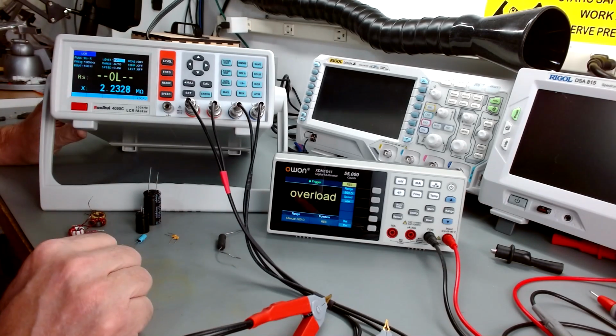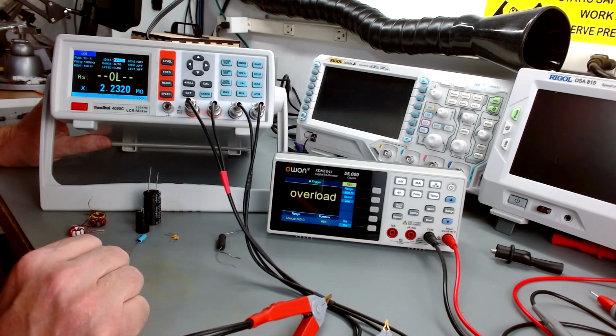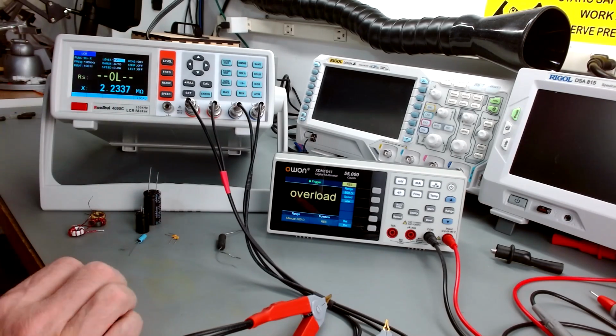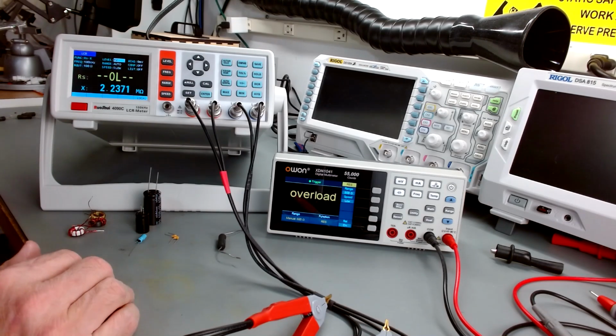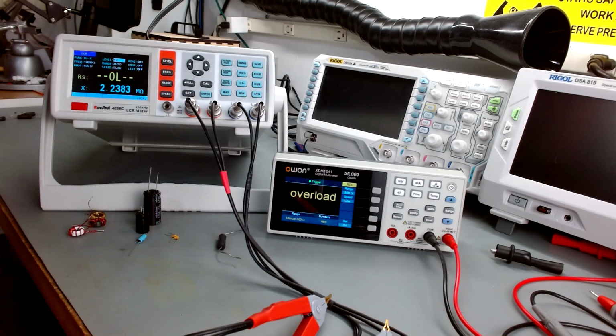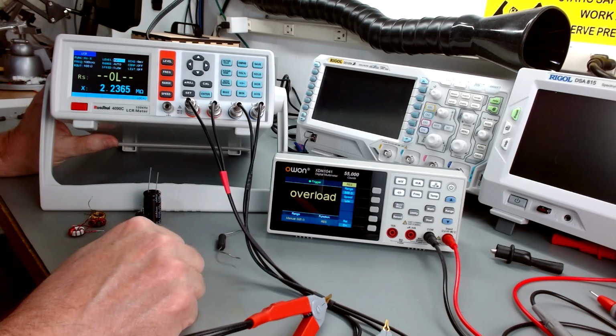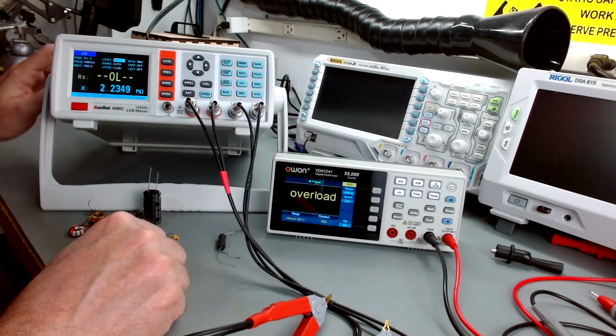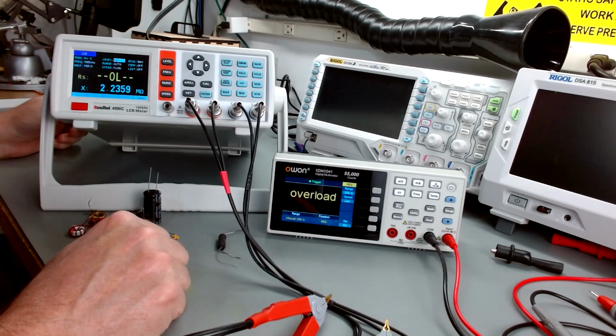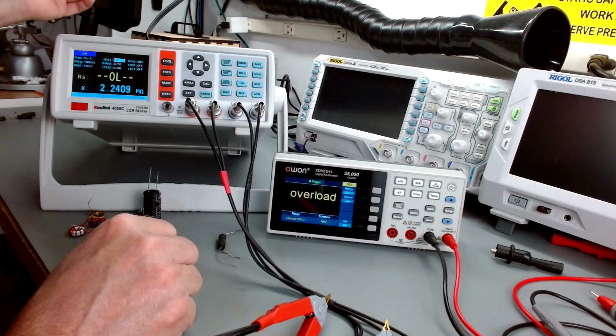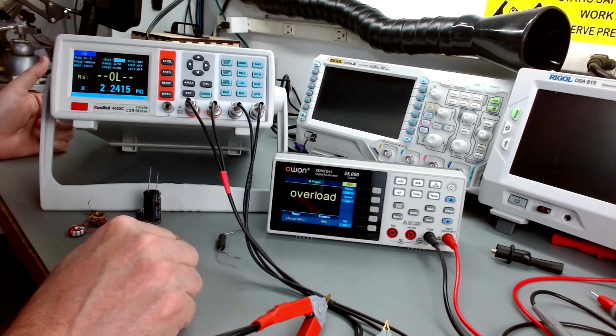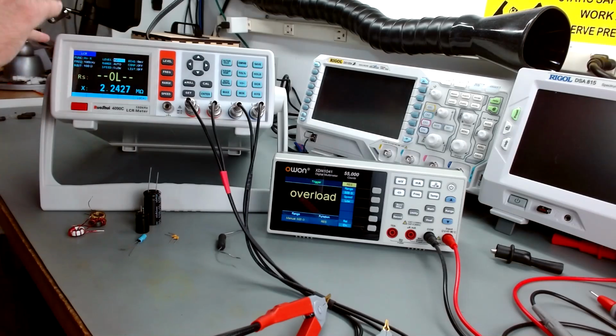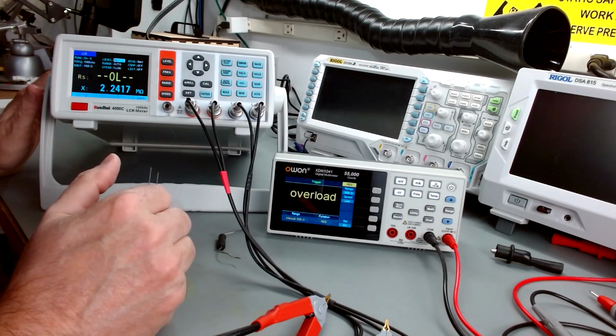Number two, really the only other complaint I can have with it is it's a little slow to calibrate. But I understand that typically you don't have to calibrate these things that often. But I have a different situation where I use my thermal test cell over here to test stuff. So I'm often hooking this to pass-throughs that have their own cables inside the box. That means when I hook this up, I've got to calibrate for it. And then when I come off of that, I'm going to use it on the bench, I've got to calibrate it for this. So I do tend to calibrate quite a bit.